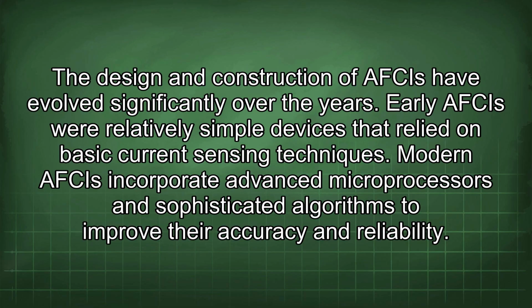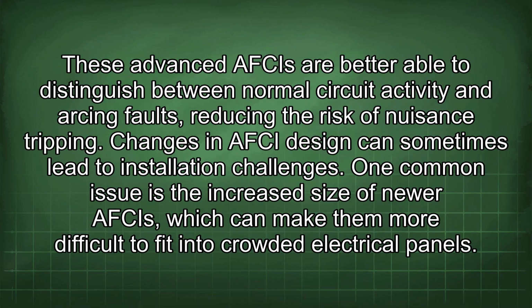Early AFCIs were relatively simple devices that relied on basic current sensing techniques. Modern AFCIs incorporate advanced microprocessors and sophisticated algorithms to improve their accuracy and reliability. These advanced AFCIs are better able to distinguish between normal circuit activity and arcing faults, reducing the risk of nuisance tripping. Changes in AFCI design can sometimes lead to installation challenges.